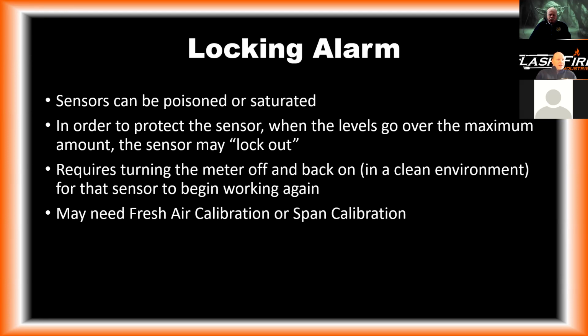So the solution for this, and what will usually happen, is you'll get either 3 pluses or 3 right angles coming up on the meter. Actually, you'll see it in the next slide showing that you went over range. And what you need to do is turn the meter off and then turn it back on in a clean environment, and that will let the meter cycle through.